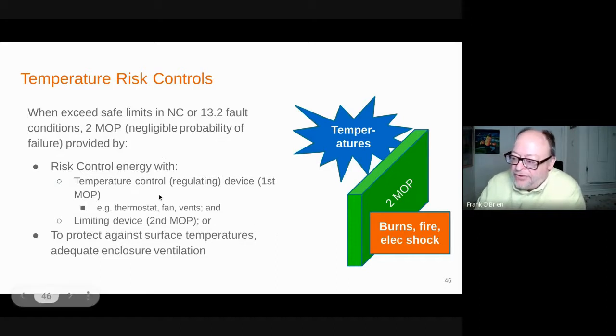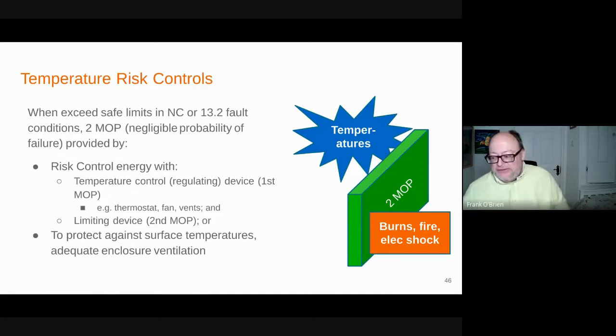Okay. So in general, if you had a heater, you want to think about single fault safe. So we call the first one the regulating temperature device. And then if that should fail, we're looking for a limiting device. I want to mention that detectability would be nice there. So you should have a manually reset limiting device. And then to protect against surface temperatures, adequate enclosure ventilation. So sometimes you might need a fan or whatever ventilation you're trying to do. And in any case, the need here is to meet your temperature limits. And then there's ways, by inherent design risk controls, you can do that, or whatever they're called.